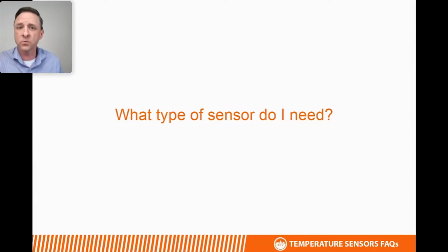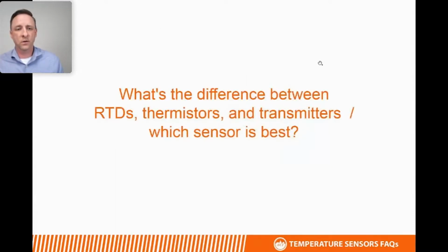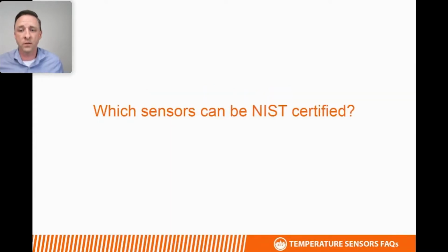And as far as which sensing element is required, the vast majority of that is a matter of system compatibility, not necessarily which sensor or sensing element is better or worse. Most PLCs and DDC systems have a standard or a default input, and we can help match up which sensor is going to ensure system compatibility with the control system that you're working with. Along those lines, the next frequent question we get is, what's the difference between RTDs, thermistors, and transmitters, and which one is best? So that's something that we'll hear pretty regularly is just give me the best one. And all of these have different advantages and disadvantages and strengths and weaknesses. So depending on the specifications of the job's requirements and system compatibility, one specific sensor or sensing element may be better or worse than others, but that's definitely something we here at ACI are happy to discuss with you.